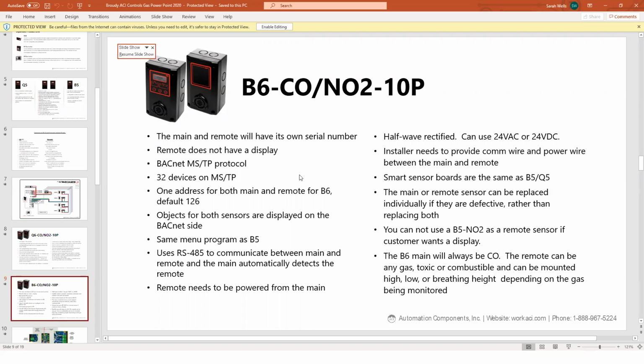Dave can talk a little about the typical wiring a customer should use. The manufacturer recommends Belden 9841 ComWire for the RS-485 runs - that has to do with the resistance of the wire. Belden 9842 or 9841 are equal, and that's really important for running the ComWire. We've run into a couple of cases where someone ran regular twisted pair instead, and it does not work.